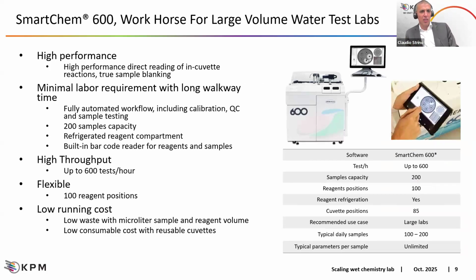So the SmartChem 600 is a really high performance unit with direct reading of in-cuvette reaction with true sample blanking. What does it mean? That the reaction will be read directly in the same cuvette where the reaction has been developed. And true sample blanking means that the sample blank, because we have the possibility, as we will see, to detect also the sample blank, is performed in the same cuvette where the reaction will be performed. So we will put the sample in the cuvette, we will read the blank of the sample, and then we will perform the addition of all the reagents needed to complete the reaction.